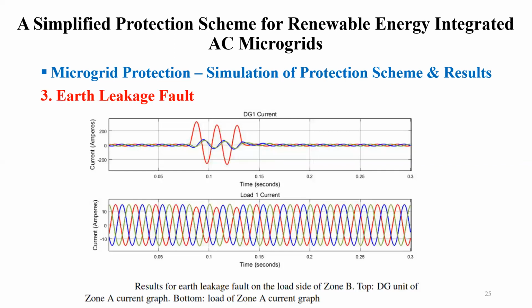Similarly, again for an earth leakage fault, in this case the distribution unit keeps on supplying, so the supply stays on. We have seen that the response time is again less than 0.1 seconds, and the earth leakage fault is removed and the distribution of the supply is resumed.